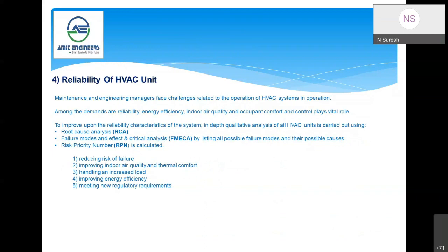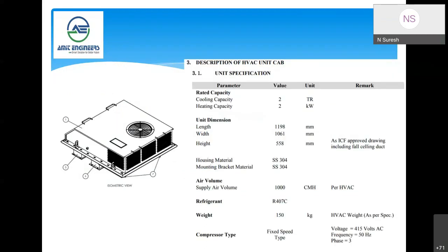We can move on to the cab air conditioners. This is the driver cabin air conditioner, with a capacity of 7 kilowatt and 2 TR. The unit dimension is 1.1, 1 and 0.5 meters. As with the saloon HVAC, the structure is stainless steel SS304, and air volume is 1000 cmh per unit. Again R407C refrigerant is used. The weight of the unit is 150 kg.